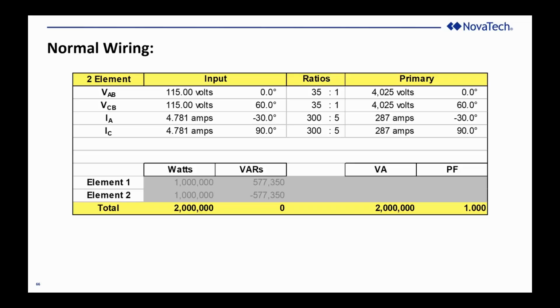I've got a 30-degree phase shift between the A-phase current and the VAB, and a 30-degree phase shift between IC and VCB, like I showed in the vector diagram a few slides ago. It should be showing me, I picked an amount of current that adds up to 2 megawatts just because it's a 2-element meter, and it's a good indicator of where your problem is.